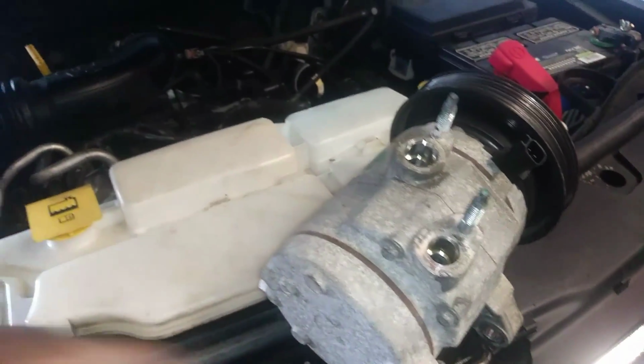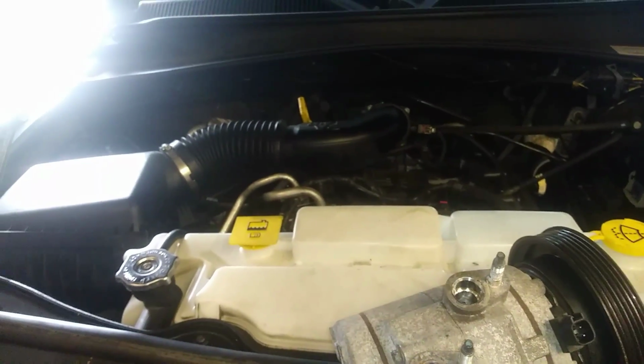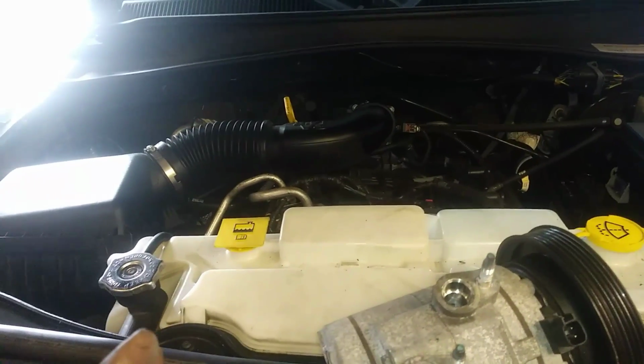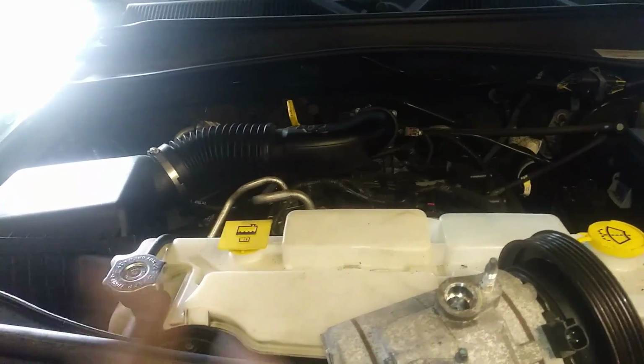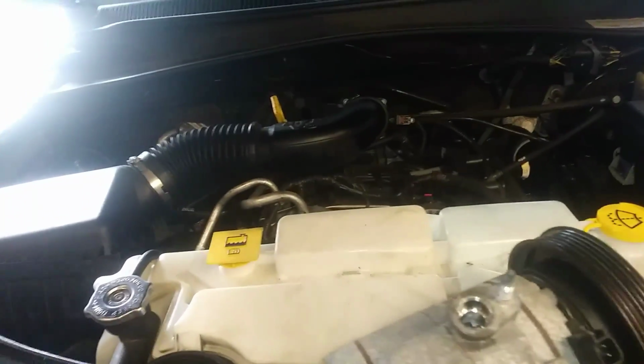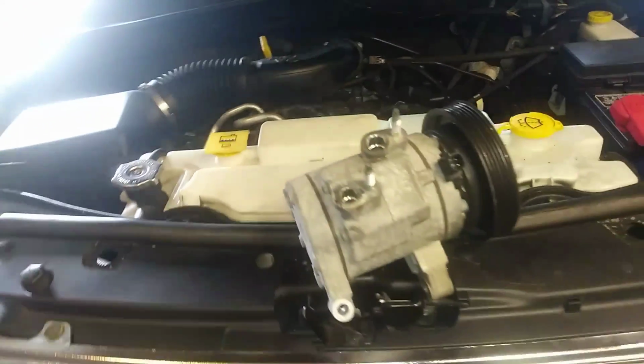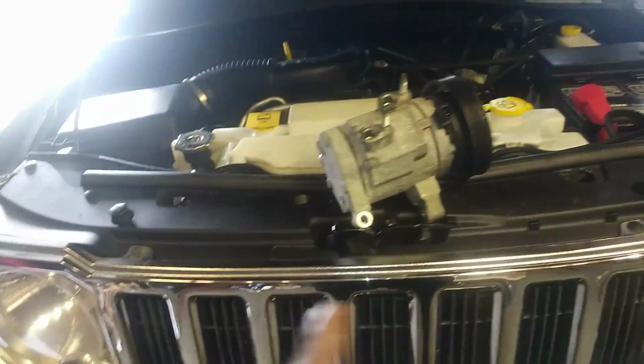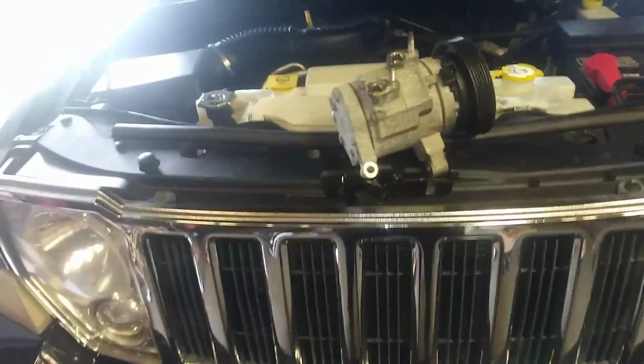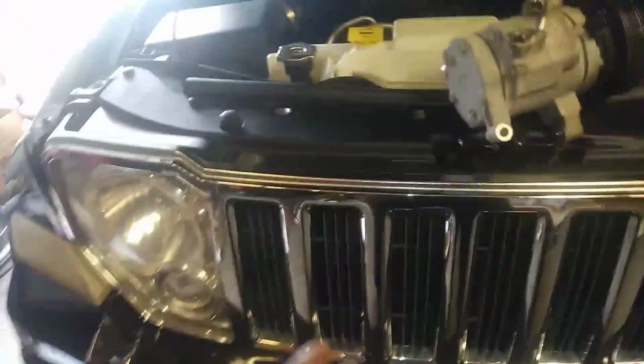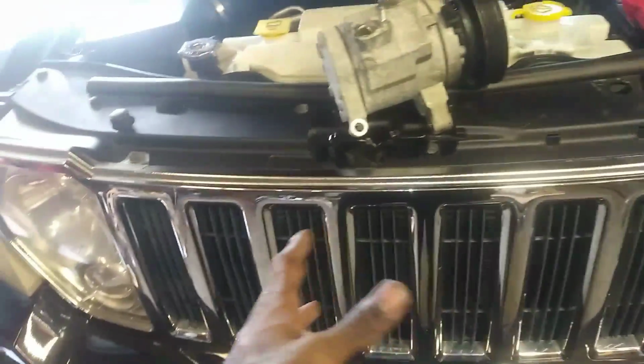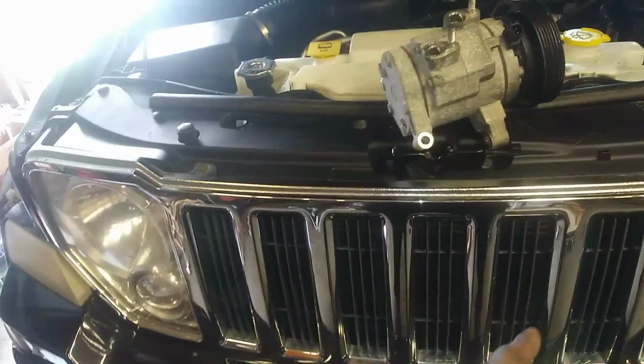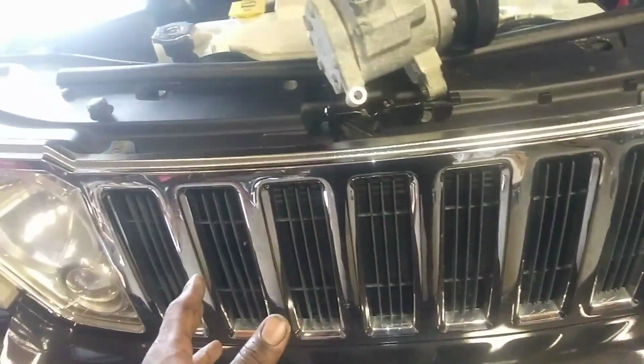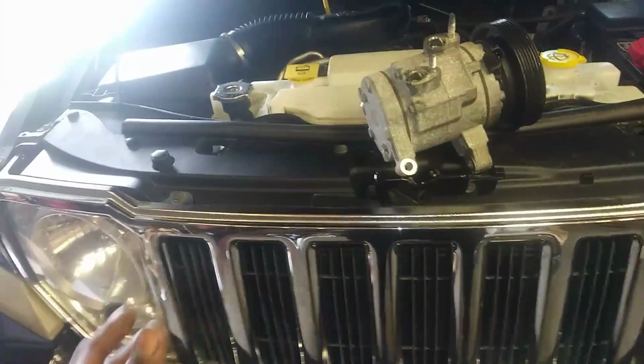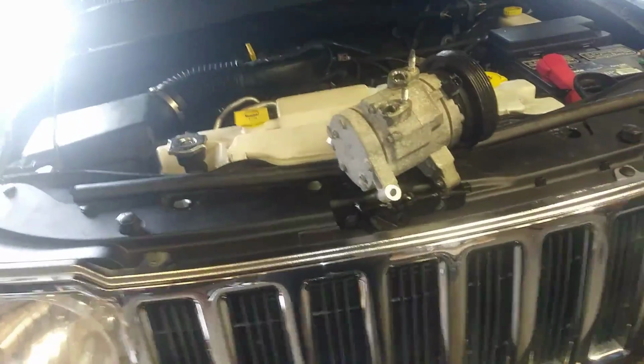But I did have to put a little bit more Freon than normal in there. I think it was supposed to hold about, what, 18 ounces. I got about 21 ounces in there. The pressures were high at one point, climbing to 500, but what I normally do as far as getting the pressure back down is put water on the condenser, and what that will clear some of that space to where it can fill those voids with liquid Freon.